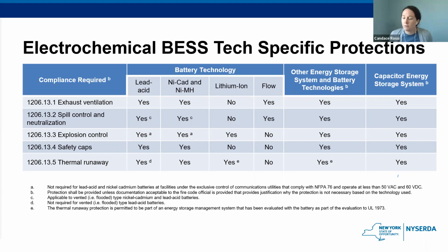So you can see the 4 different battery technologies that they've called out as part of the code. Lead acid, nickel, lithium ion, and flow. Lead acid is required to meet all of the compliances that you see on the screen. Same with nickel. Lithium ion is only required to meet the explosion control and thermal runaway compliance. And as we go through each slide, I'll kind of give you an idea why that is. And then also flow doesn't require the last 3 as well. Basically, if your storage system is not located here, you will need to meet all of the compliances unless you can provide some sort of justification of why it's not required.